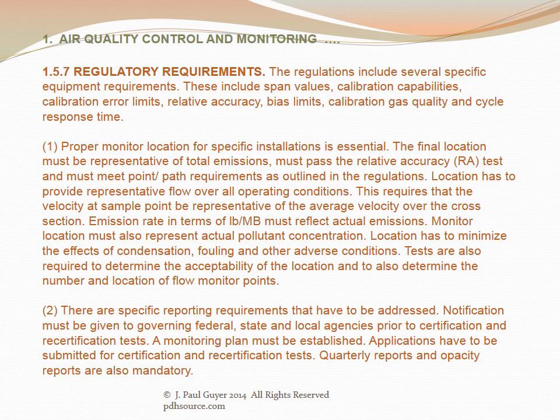The regulations include several specific equipment requirements, including span values, calibration capabilities, calibration error limits, relative accuracy, bias limits, calibration gas quality, and cycle response time. Proper monitor location for specific installations is essential. The final location must be representative of total emissions, must pass the relative accuracy (RA) test, and must meet point and path requirements as outlined in the regulations.